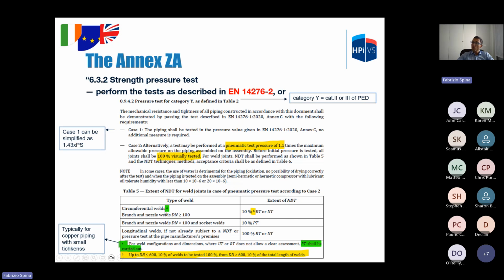NDT on circumferential welds must be done on 10%, by radiographic examination or ultrasonic examination. It depends on the DN. It could be 10% of the number of welds or 10% of the total length. It depends. And also, for weld configuration and dimension, when UT or RT doesn't allow a clear assessment, PT, so dye-penetrant examination, shall be carried out. This is typically for copper piping with small thickness. So the outcome is basically the same as the previous slide: 1.1 pneumatic test and 10% NDT.